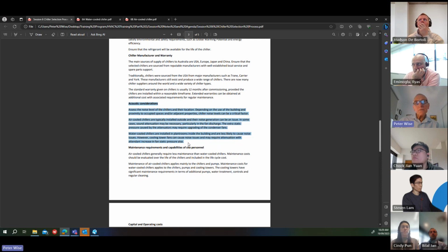Water-cooled chillers are installed in plant rooms inside the building and are less likely to cause noise issues, but the cooling tower fans can cause the noise issues and they may require attenuation also. So you need to look at the static on the cooling tower fans, and we talked about that last week.